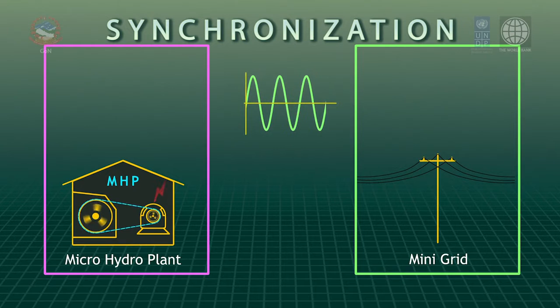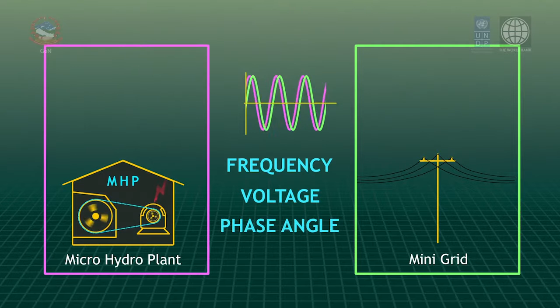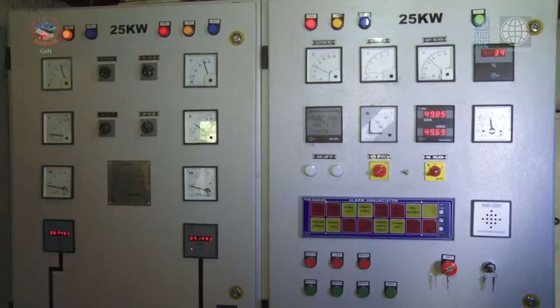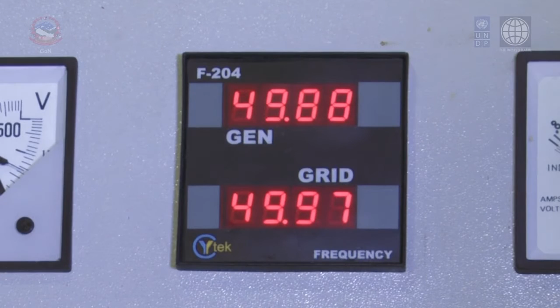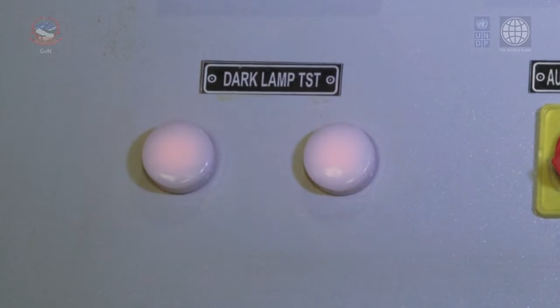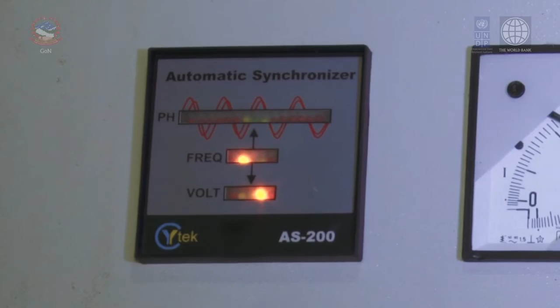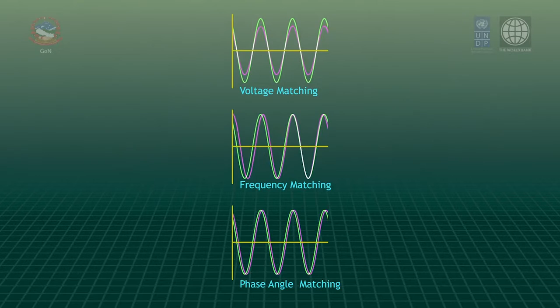Synchronization is a process of interconnection of the generator to the mini-grid when the three electrical parameters, namely frequency, voltage, and phase angle of both of the sources are matched together or lie within a predefined limit. These parameters are displayed by the combo displays, which show the readings of the generator and the grid together. The dual frequency meter displays the frequencies. The dual voltmeter displays the voltage, whereas the dark lamp shows whether the sources are in phase or not. The LED indicators on the automatic synchronizer show the matching progress. When all three parameters match, the AC contactor is activated and the generator is connected to the grid.